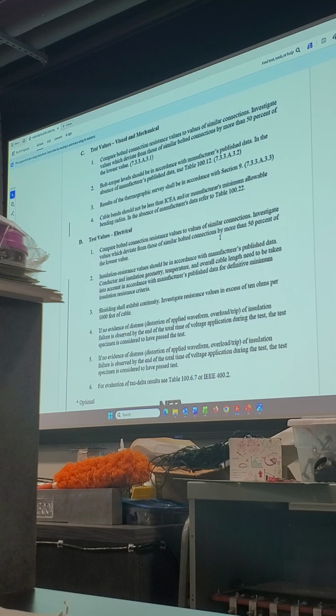Remember, the first set of slides said that DLRO should test that equipment has not gone above acceptable values. So this is our benchmark for what an acceptable value is. We're going to take actual numbers to it, and eventually, probably in this class at this time, we're going to get a set of values that we can actually apply the 50% rule to.